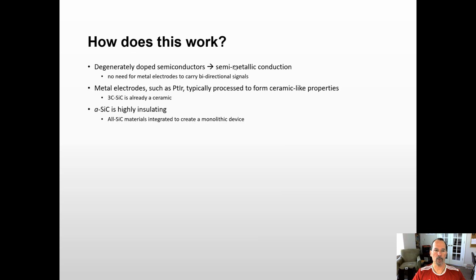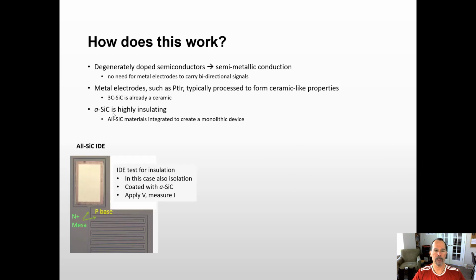So again, how does this work? I just mentioned the semi-metallic conduction of the heavily doped N+ layer. A lot of devices use, for example, platinum iridium sputtered or coated on the recording tip to give it ceramic-like properties. Well, cubic silicon carbide is already a ceramic, even though it's a semiconductor, so we don't need to add an extra coating that can over time delaminate and fail. And again, we have this amorphous silicon carbide that's highly insulating.